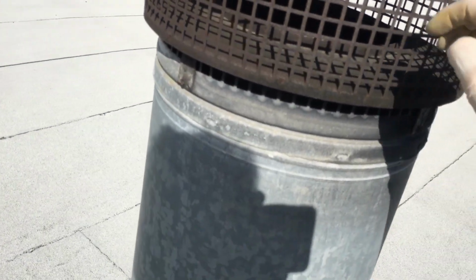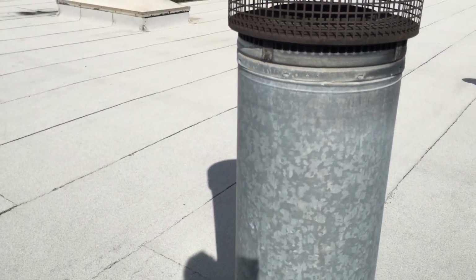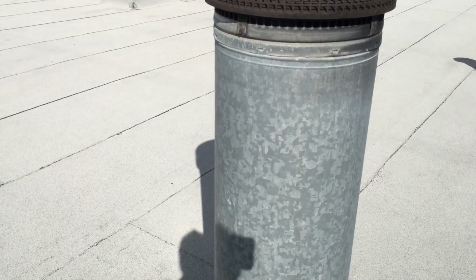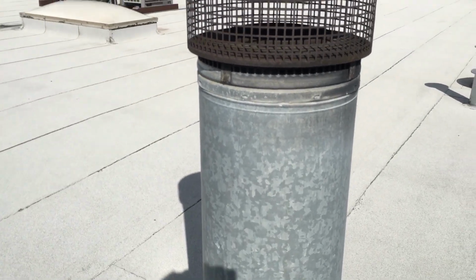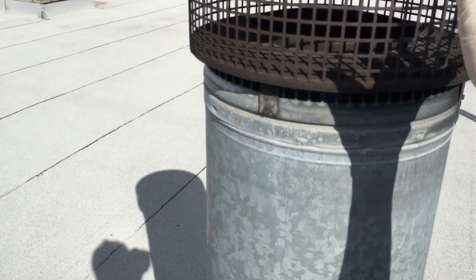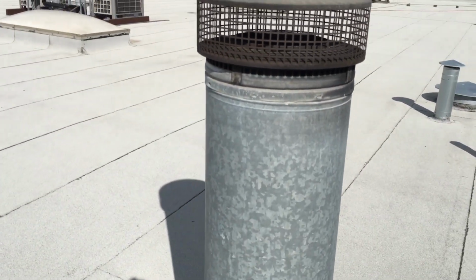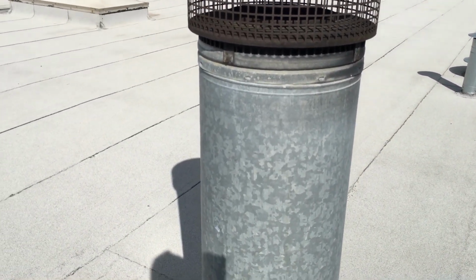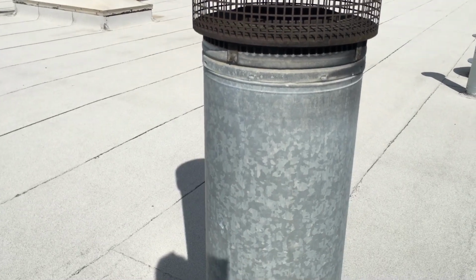These are still exiting, making the building negative. This literally pulls backwards. So when I was coming to this business and I would enter the front door in the office, I get hit with this heat. But what I also notice is the amount of water in the air. It's like 80 or 90% humidity in that room, and that's why they were feeling warm, because instead of all the exhaust coming out of here and fluing up after it got hot, it was literally going back in, and he's sitting there at his computer doing work, all nice, warm, and cozy.